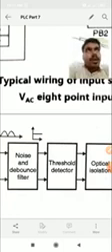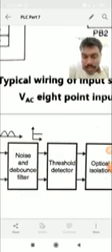Means we are giving a predetermined value. Let's suppose out of 230 volt, 110 volt should be reached, so 110 will be the threshold value. After that only the process should turn on and off. A typical example: if the voltage is between 20 to 30 volt AC, then the state will be off. And if the voltage range is between 80 to 132 volt AC, then it will be on. So this is the threshold detection.